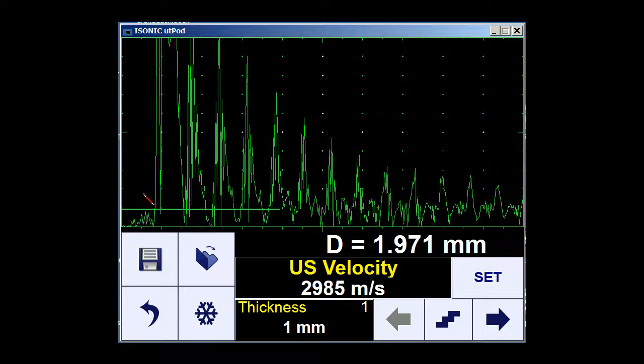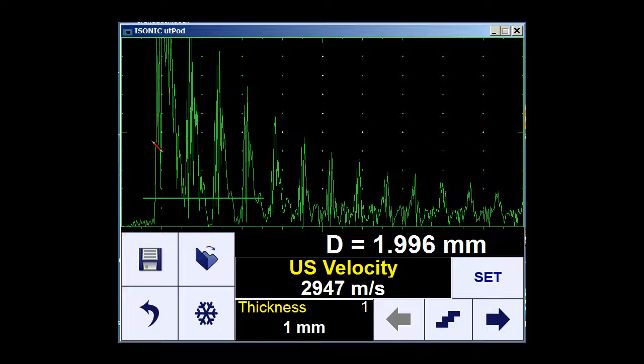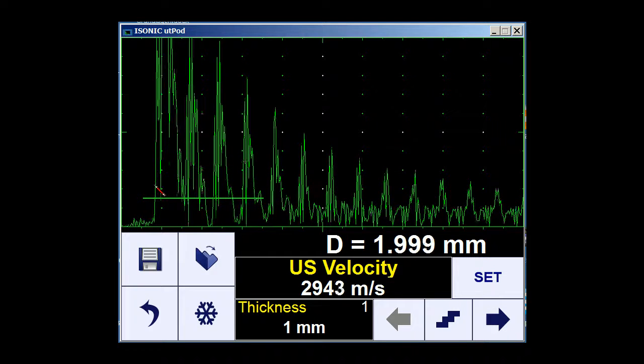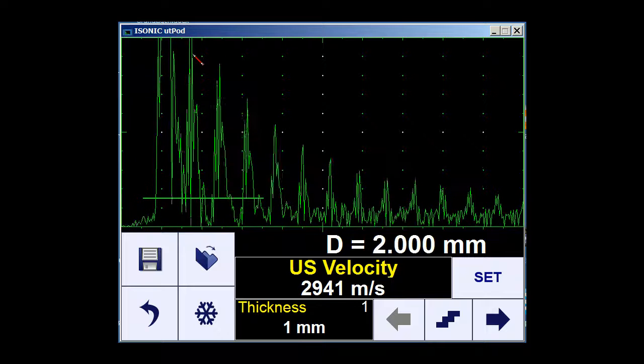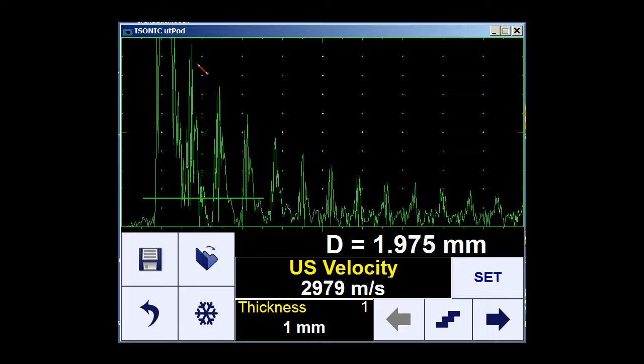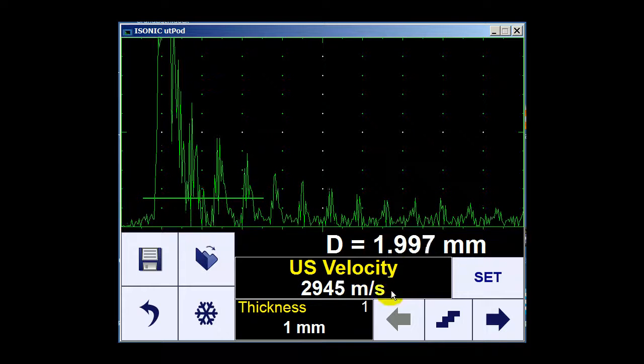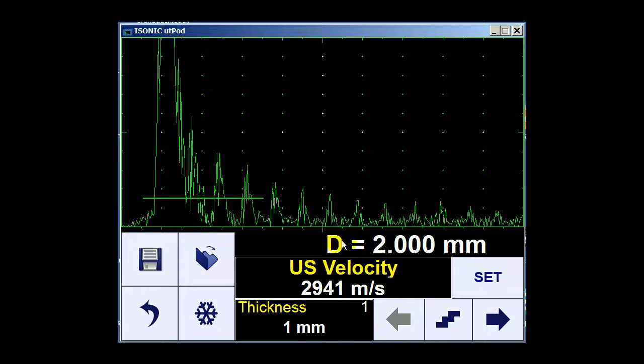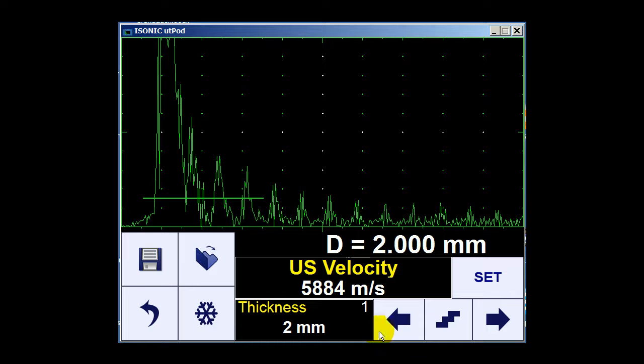I define my gate. The gate has to cover the delay line echo and at least one echo from the backwall of the test piece. Now it shows some sound velocity which is of course wrong and some thickness measurement. I am coupled on a 2mm block, so I have to select 2mm here.